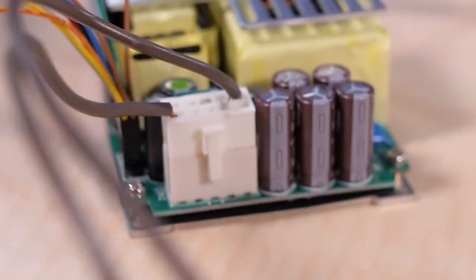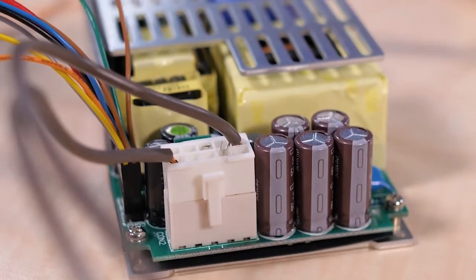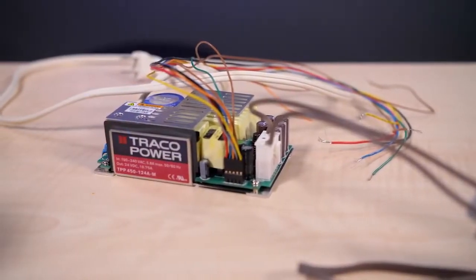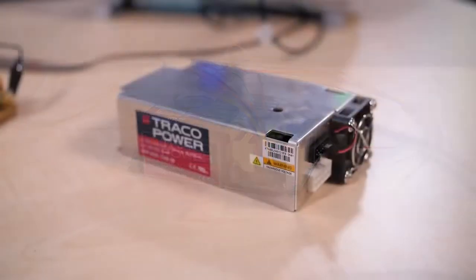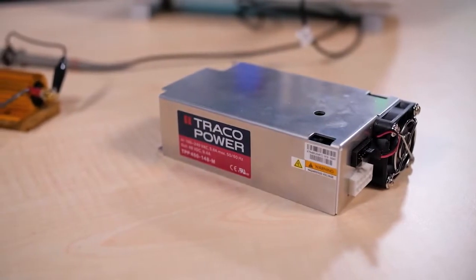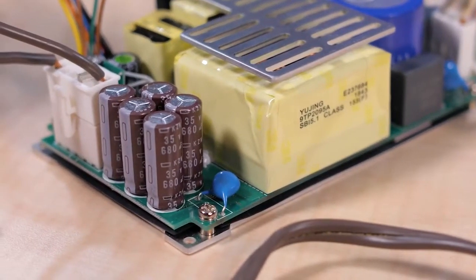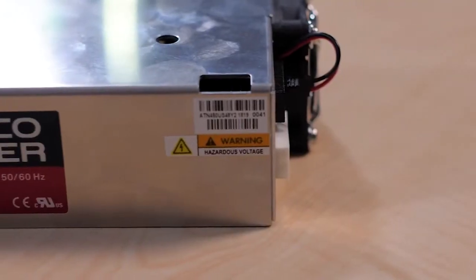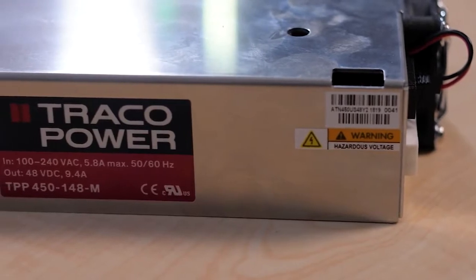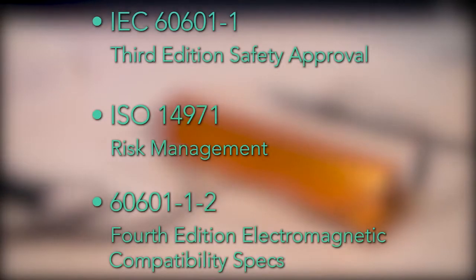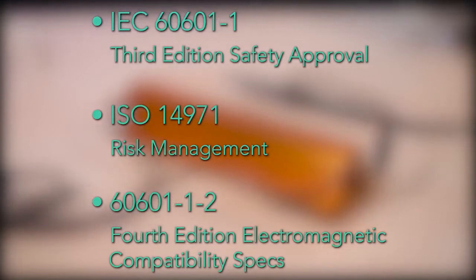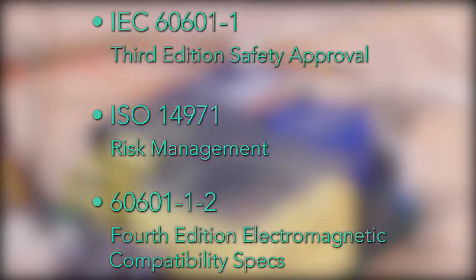These supplies have medical certifications along with IEC UL 62368-1 approval for more general purpose uses. They all limit earth leakage current to below 100 microamps, which lets them handle body floating applications. Other operational parameters that come out of their medical certification include operation to at least an altitude of 5,000 meters and meeting a workmanship standard called IPC-A-610 Class 3, which is more stringent than the default standard. They also have IEC 60601-1 3rd edition safety approval and comply with the ISO 14971 risk management and 60601-1-2 4th edition electromagnetic compatibility specs.